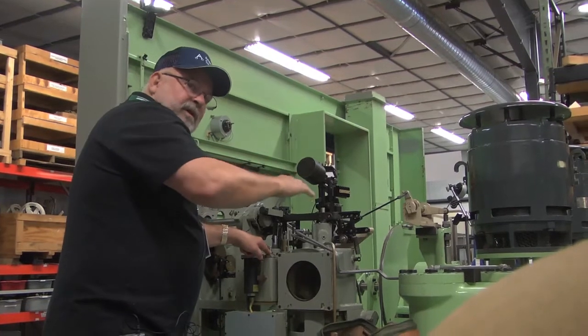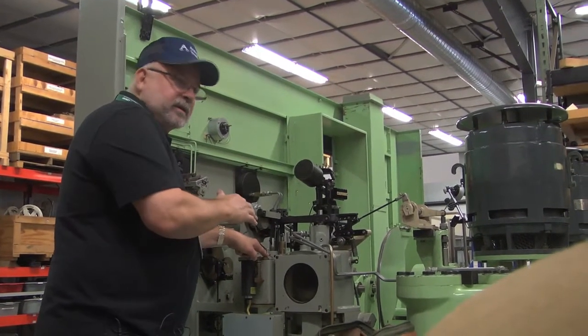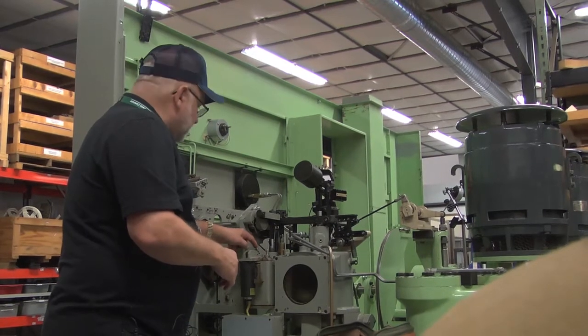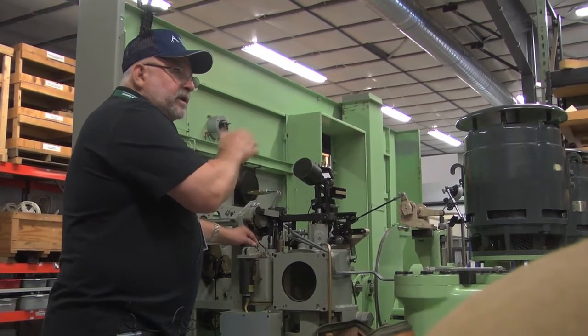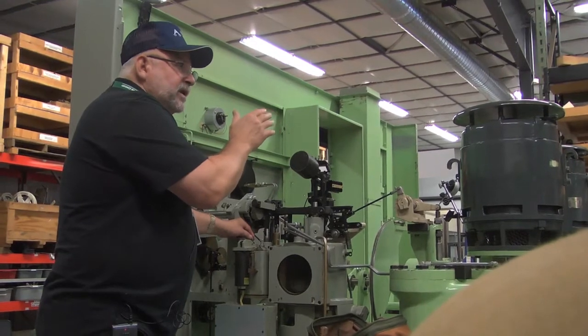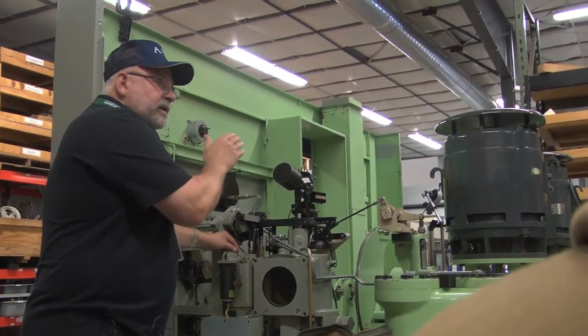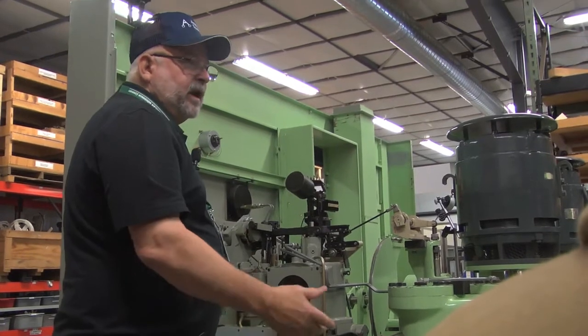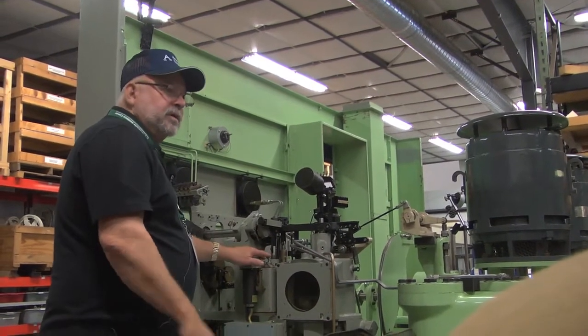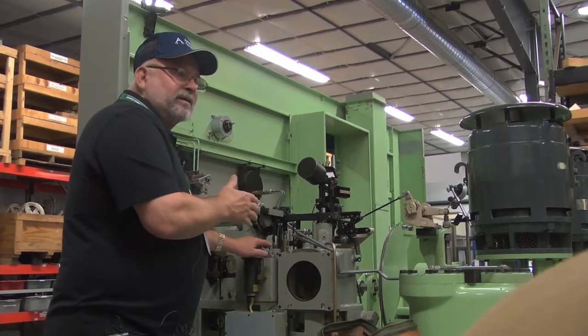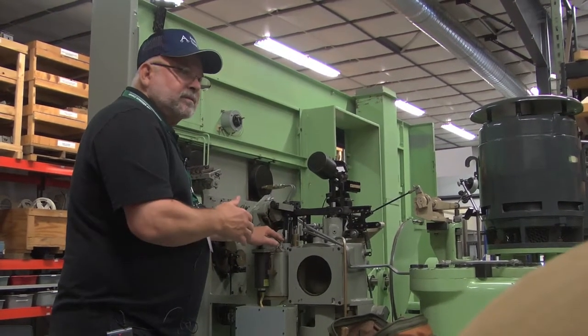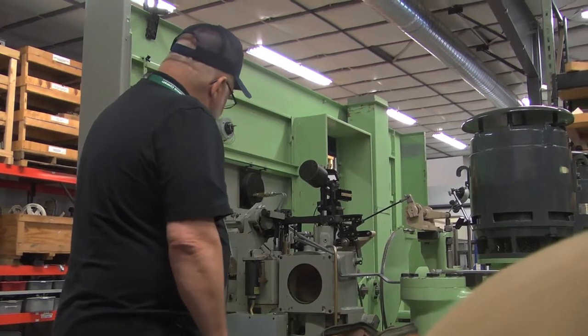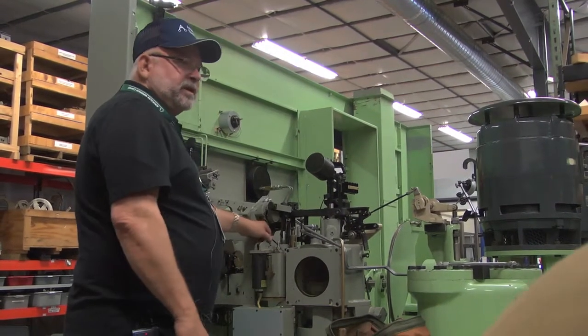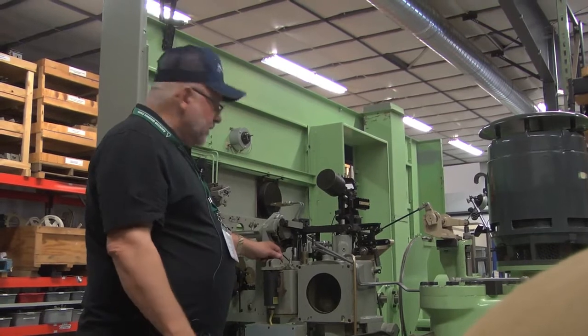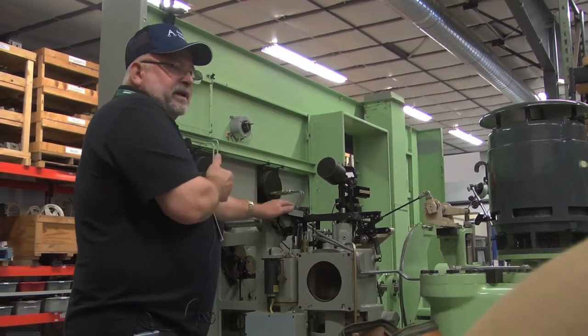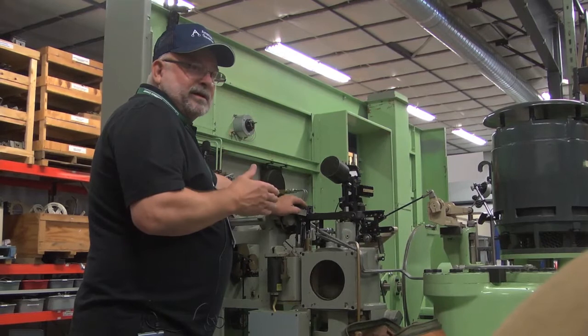I can run it down with a limit and see my 1.5 cycles real good on this one. Then I energize this, and I take this until I start seeing it hunt just a little bit, and then I take it down to where it's just not hunting. And then it has plenty of gain for online gains. Because all this is supposed to do is take away the same amount this is open. I'm sure they had this one set that way so they could show the action better. And you have to realize that this is dummied in speed, so it's not what you're going to see when you calibrate.